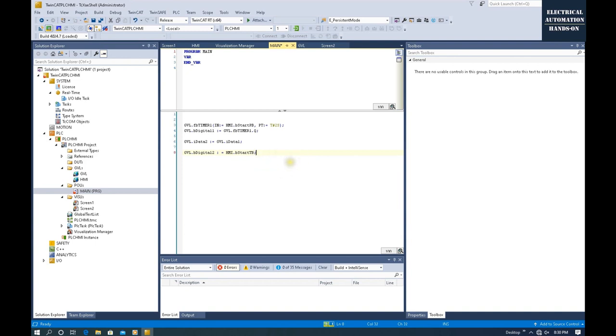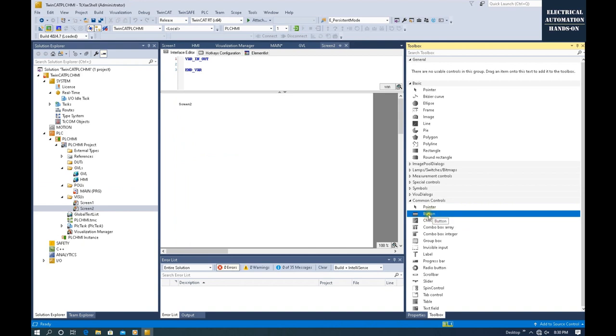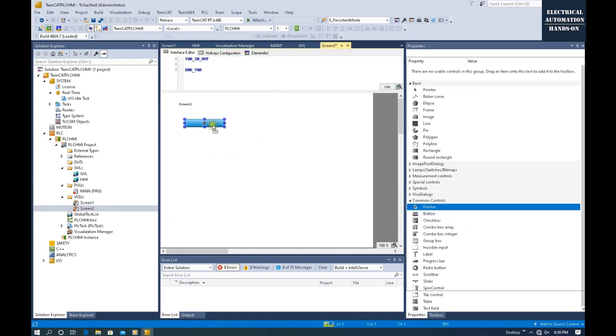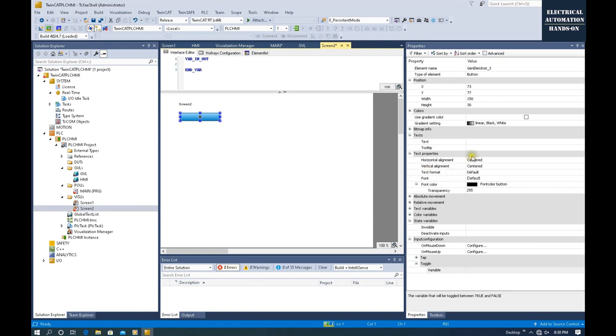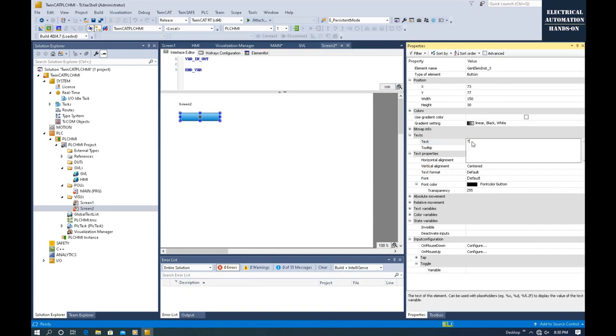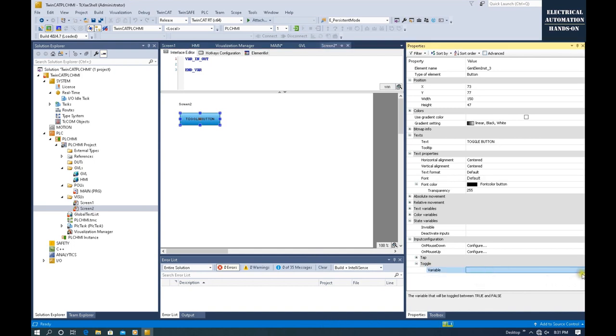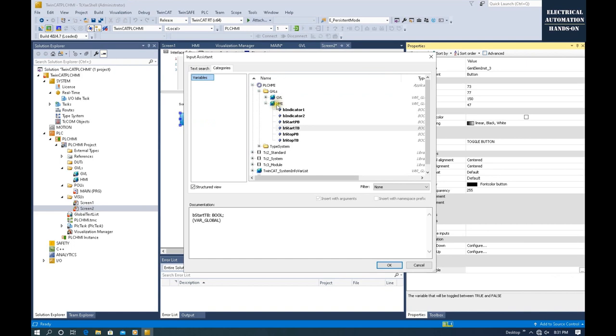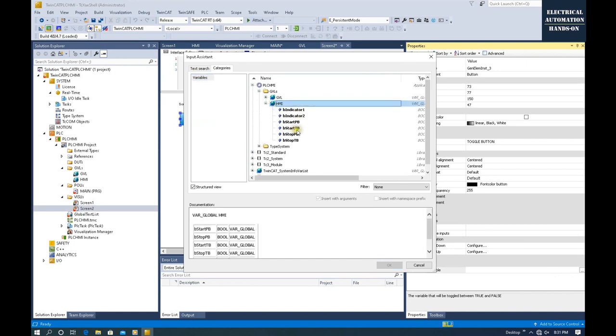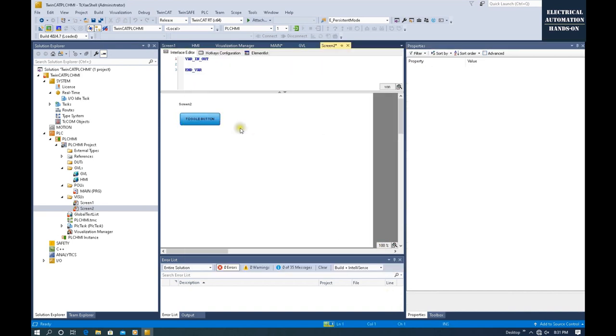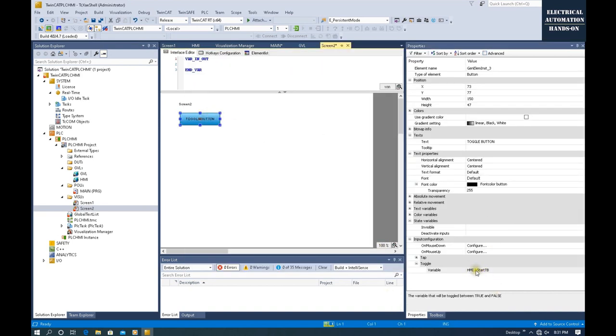Let's go to Screen 2. Now let's drag a button here. We will name it 'toggle button' and make it bigger. To use the toggle function, go to the toggle property. From this variable, let's connect that toggle tag — find the HMI toggle variable start TB. So we connect this variable. When we use the momentary function, we use mouse down and mouse up. Now we are using the toggle function.